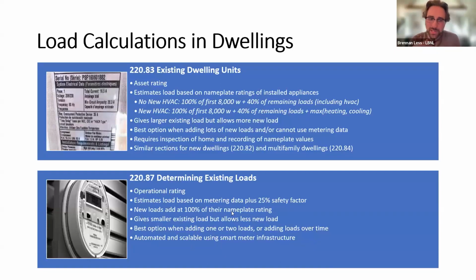This approach usually gives us smaller loads, but then lets us add less new load, because we're treating it at 100% instead of 40%. This might be the best option if you're just trying to add one or two loads, or if you're adding loads over time — you can iteratively do this calculation and might be able to fit more loads on that panel safely.